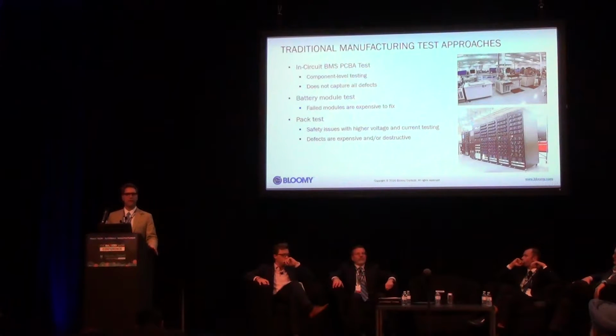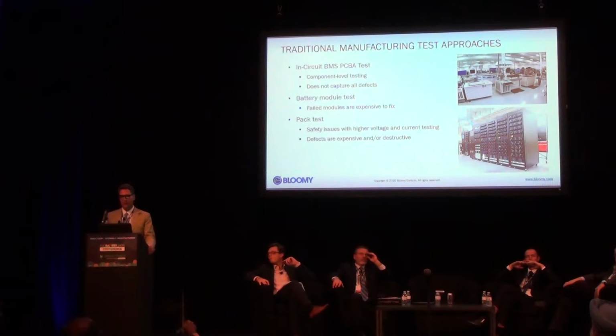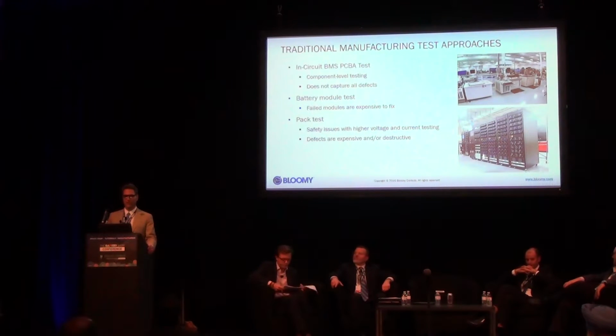It does not capture whether all of these components are integrated and communicating properly, whether the software is tuned properly, whether everything is receiving power and the conductors and connectors are applied properly, and that everything is working together is not assured when all of these components are tested using in-circuit testing. And that's a big risk, especially for a complex piece of equipment that has hardware and software, like a BMS with control algorithms and such. So that's a risky proposition of relying just on in-circuit testing.